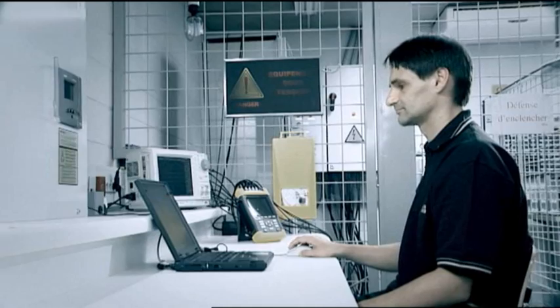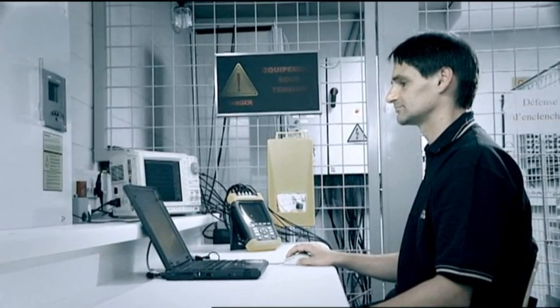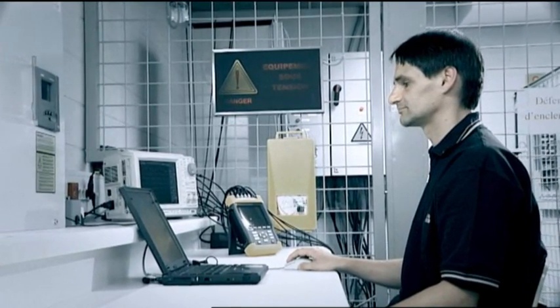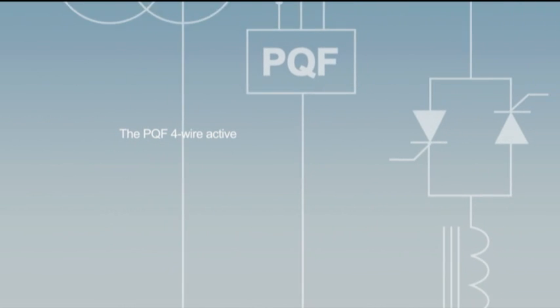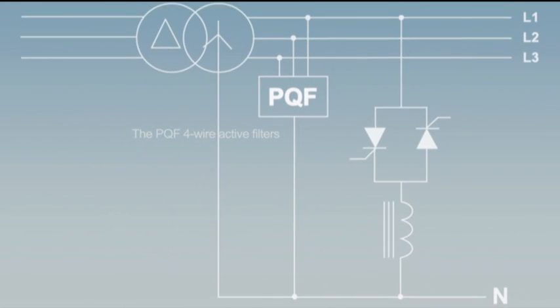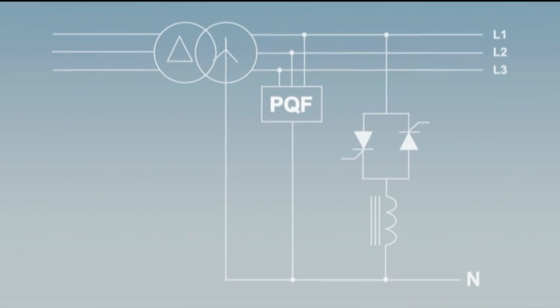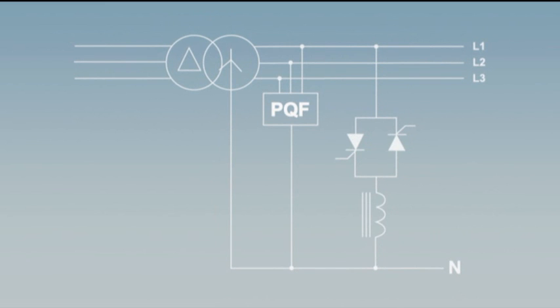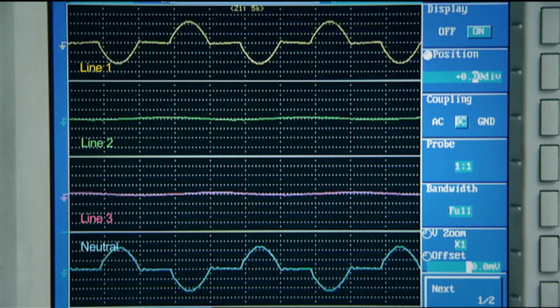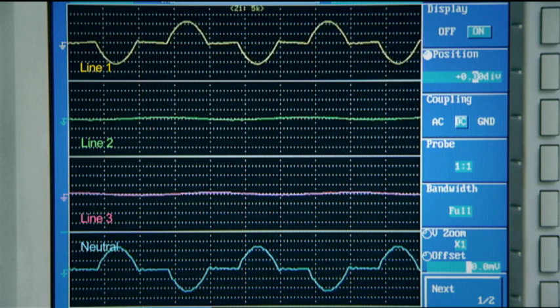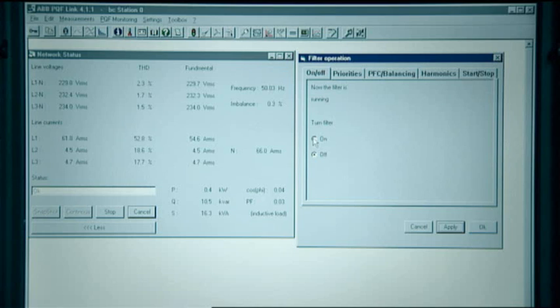In a second demonstration, we will now show the load balancing features of the PQF 4-wire active filters. A single phase harmonic load is connected between line 1 and the neutral. As a result, the supply current is highly unbalanced and distorted with about 60 A flowing in line 1 and the neutral and about 5 A flowing in the other lines.